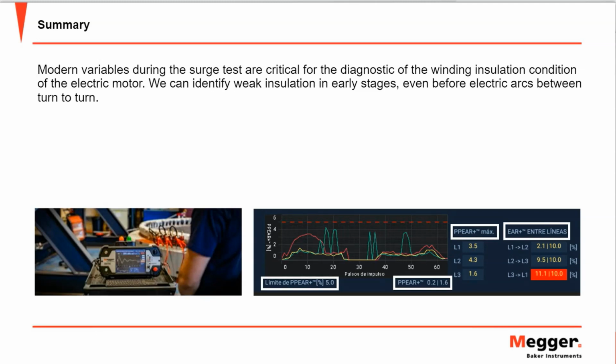In that way, we can reduce the warranties for services during maintenance or repair. This is very useful for motor repair shops, because I can say, Mr. Customer, I did the maintenance of your motor, I put it in the furnace, painted it, but this information is telling me that we are pretty close to passing the thresholds and we will have arcs in the motors.